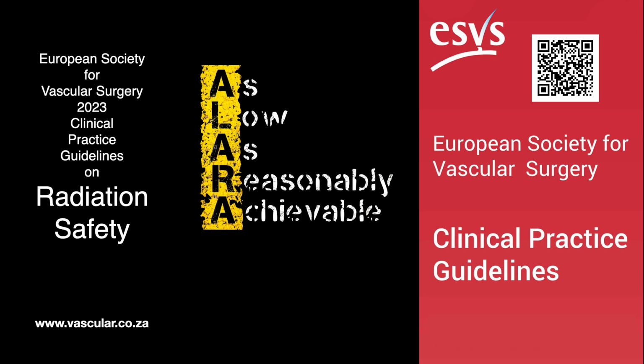So we've talked about dose units and the risks. Let's take a moment to just quickly recap the key measurement concepts. Good idea. We've got air kerma, AK, which is like the intensity hitting the patient's skin, measured in milligray, usually at that patient entrance reference point. And then air kerma area product, KAP or DAP, measured in gray centimeters squared. That's the total energy in the beam. Right. And these two, AK and KAP, are much better than fluoroscopy time for actually tracking radiation dose objectively, because FT doesn't account for settings or mode. And we should compare our KAP values against national diagnostic reference levels, DRLs. Exactly. Use DRLs as a benchmark for optimization.